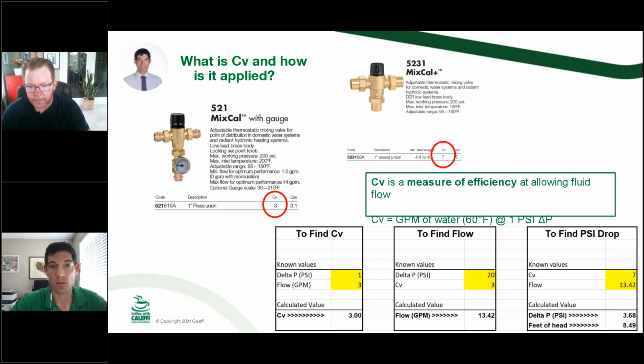So now let's say we switch to the bigger valve, the graphic on the bottom right there. It has a CV of 7. Our max flow that we need is 13.42 GPM. It only has a 3.68 PSI drop.